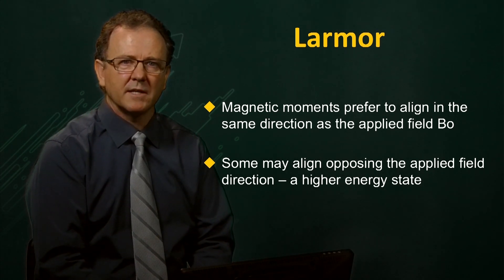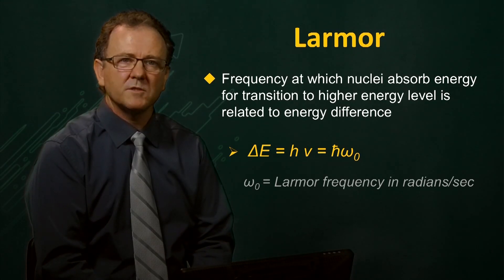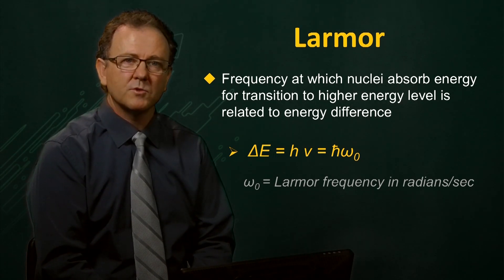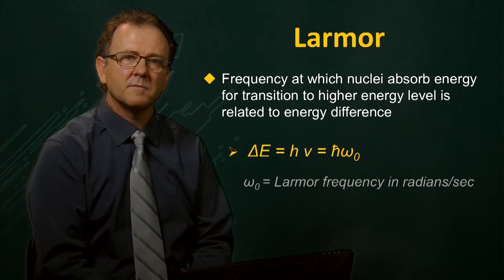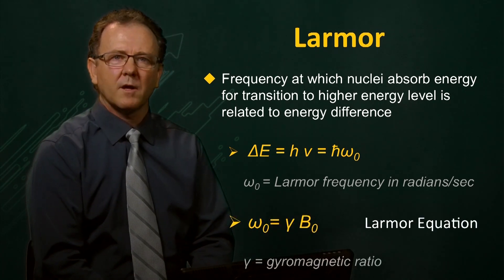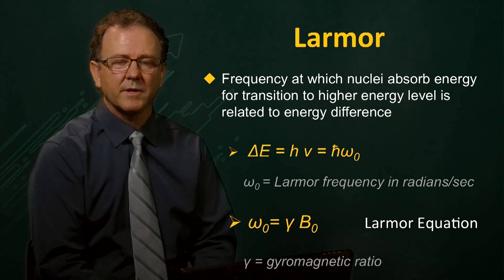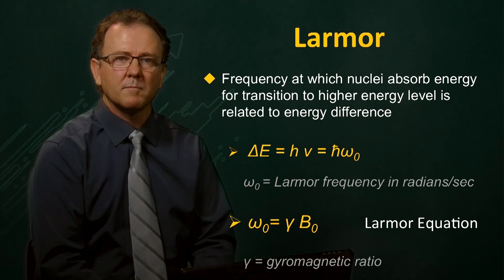While the magnetic moments prefer to align with the applied field, some may align opposing the magnetic field. This orientation is a higher energy state than when the spins align with the field. Planck's law tells us that the frequency of the energy absorbed by the spins to make a transition from the low energy level to the high energy level is directly proportional to the energy difference between the levels. This frequency is the Larmor frequency mentioned earlier. Since the energy difference is directly proportional to the applied magnetic field strength, we know that the Larmor frequency is also determined by the field strength, B0. This relationship is perhaps the most important principle in MRI and is called the Larmor equation.